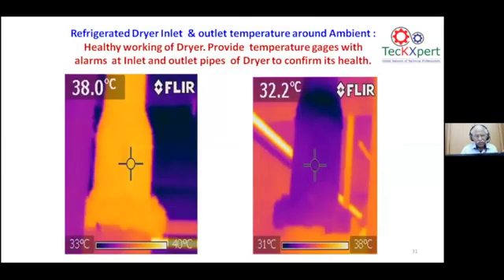Then comes the refrigeration dryer, where the inlet and outlet temperature is around ambient. Ambient is around, say, 35 degrees, the compressor delivery temperature is around 38 after the post air cooler, and after the dryer it should be around 32. This temperature monitoring is definitely needed now, especially for refrigeration dryers. You can have in situ temperature gauges on the inlet and outlet. You don't need to monitor by infrared thermal imager each and every time. You can fix in situ gauges on the inlet and outlet lines. This will show whether the dryer is working healthy or not.